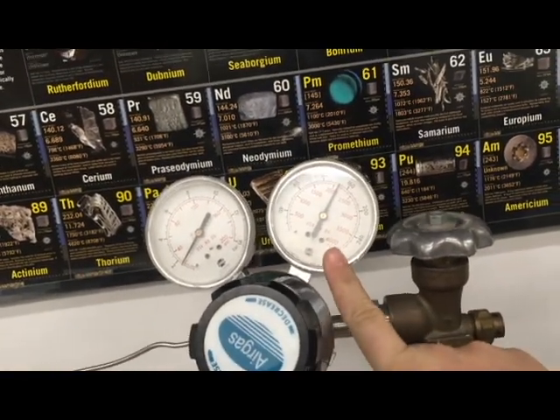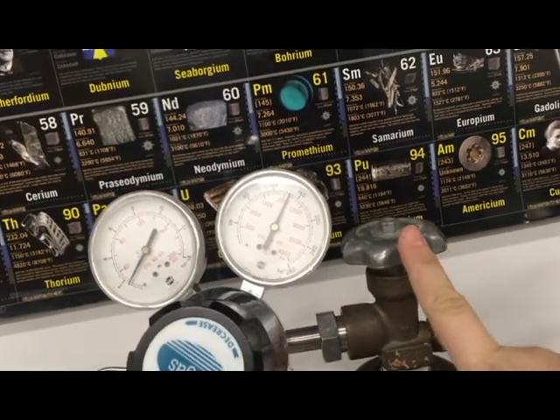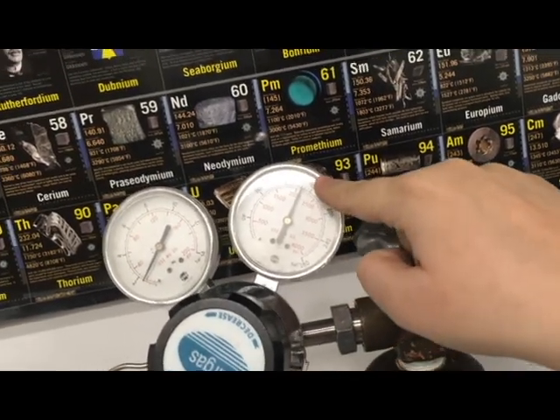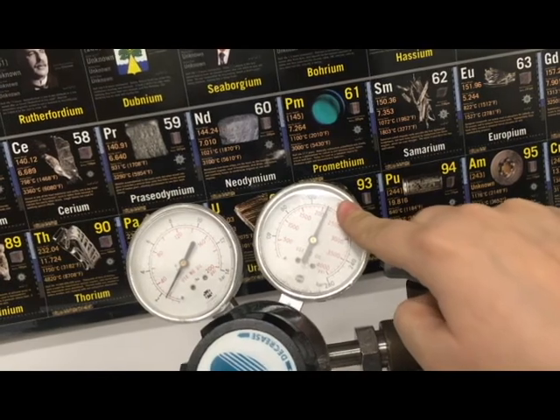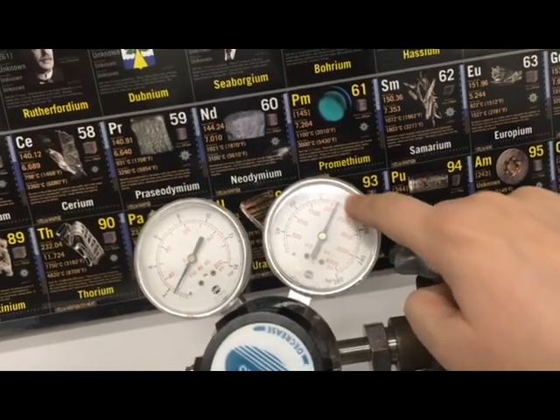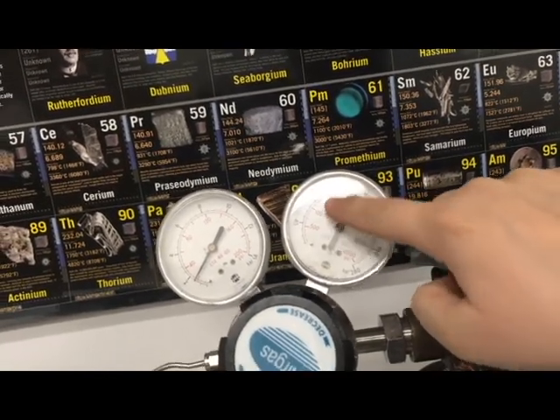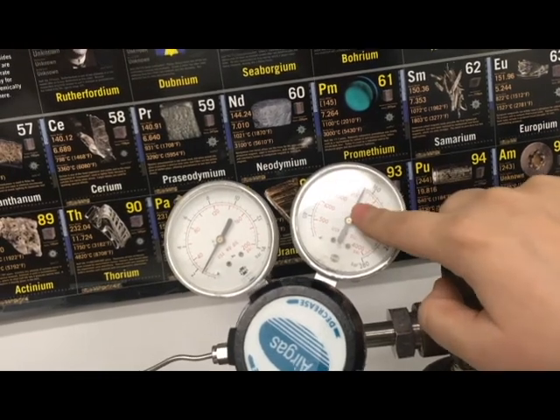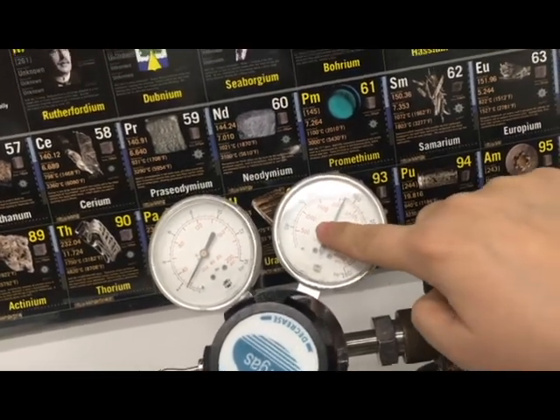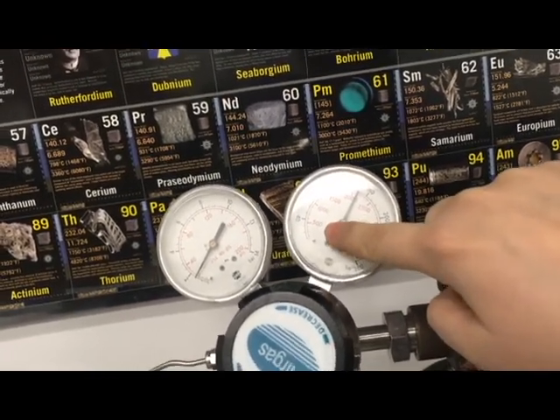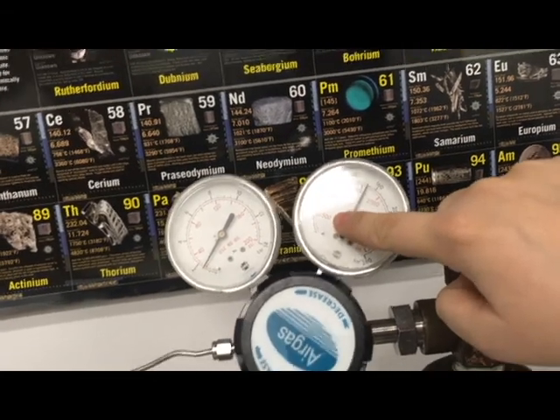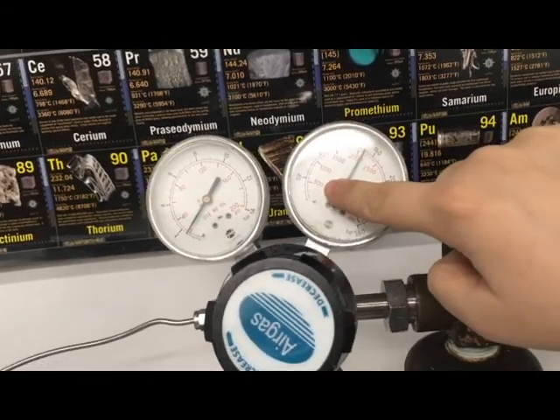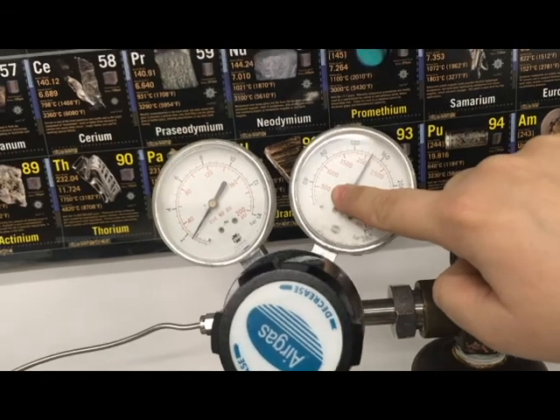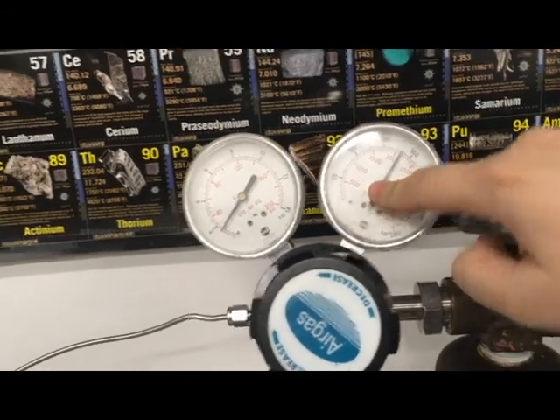This right here reads the pressure in the tank as long as this is open. Right now you can see we have a little over 2000 psi. That means this is a fairly full tank. As with any gas in the MCL, if you ever see the first regulator closest to the tank get down to 500 psi or lower, that's where we consider it to be empty, and you should contact lab staff or talk to someone who can order a new one for the lab.